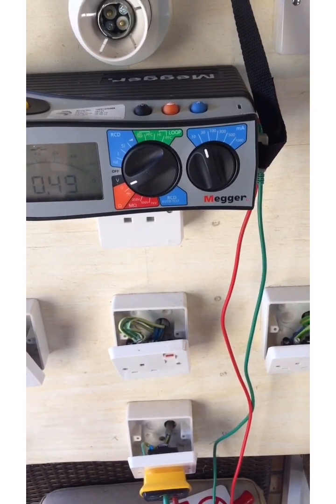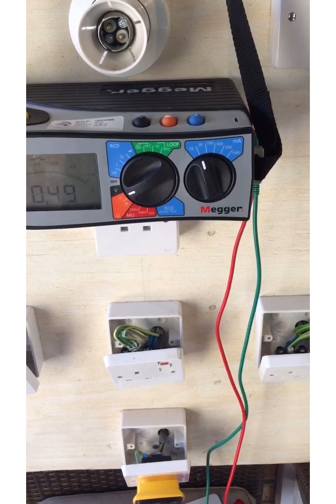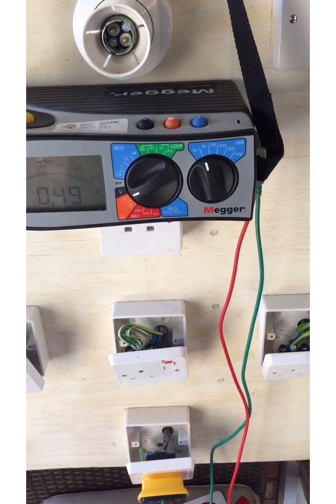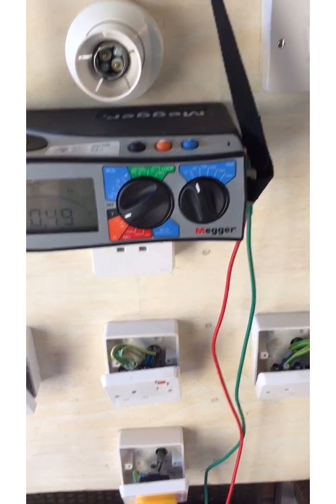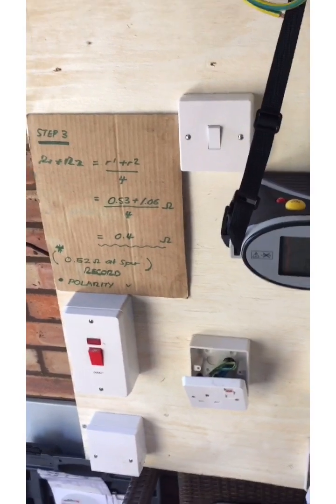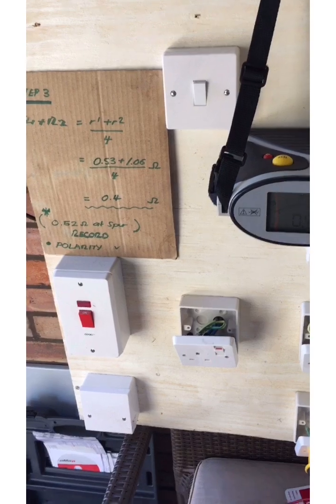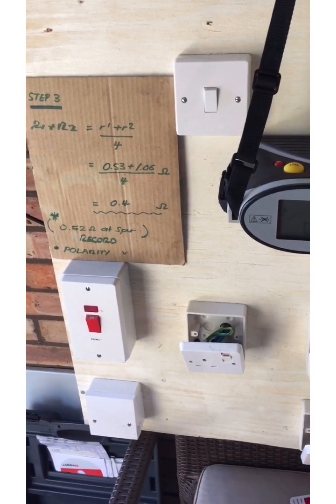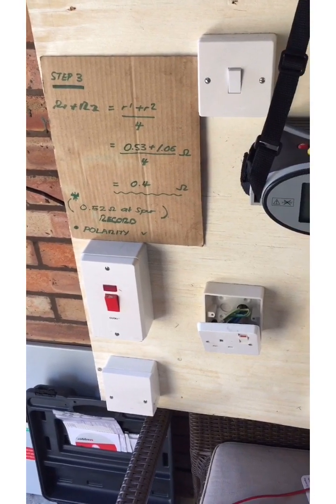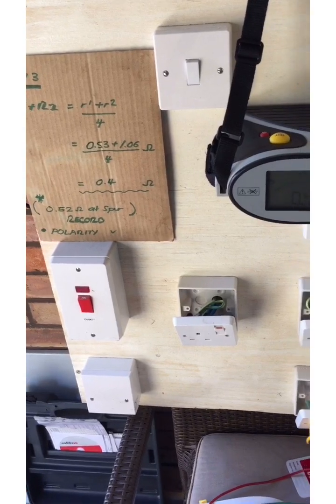When we do step two it proves that line and neutral are at the bottom two barrels and it's only when we do that third test that it proves that looking at it from the front that the right hand side has got to be the live. There's quite a bit to take in with this particular test and when I'm teaching electricians in class it tends to be this one that they struggle with because there's quite a lot of information coming at you but I suggest if you're trying to get a grip of this to watch it quite a few times and get it right into your head and try to understand every step.